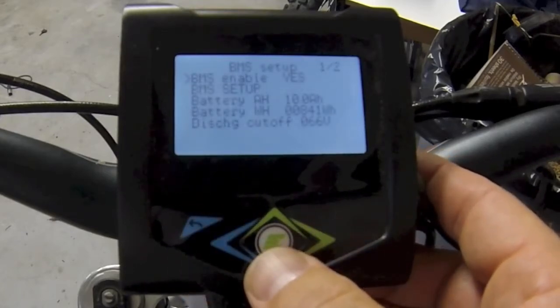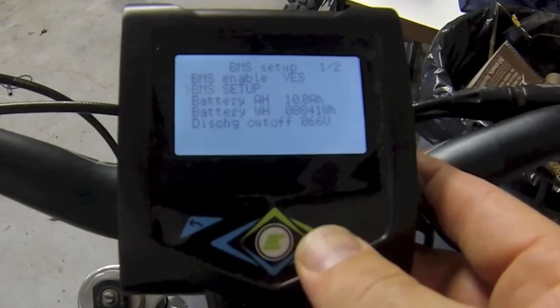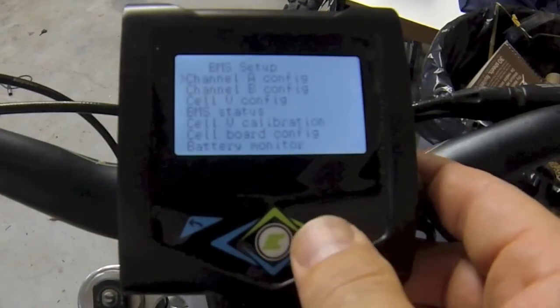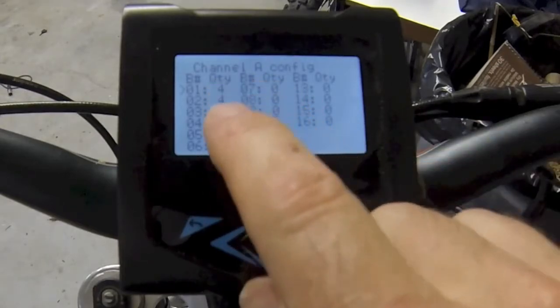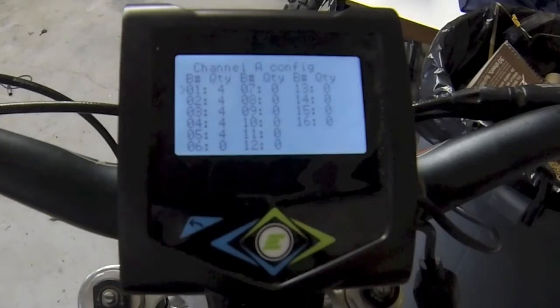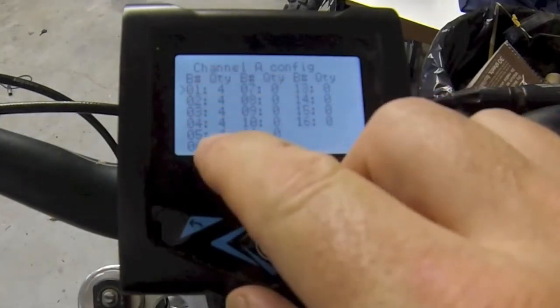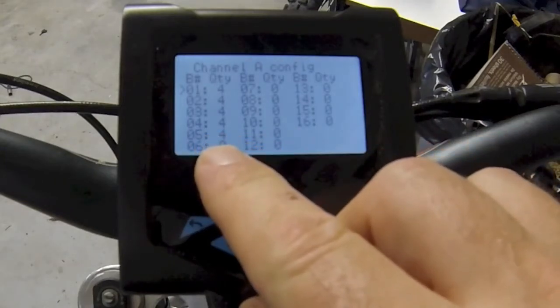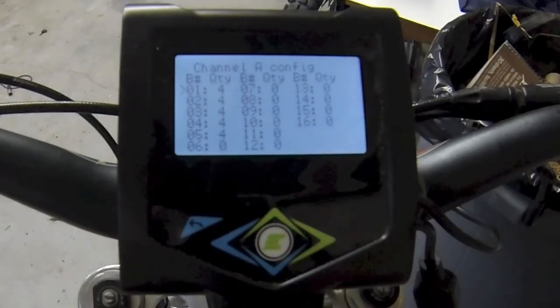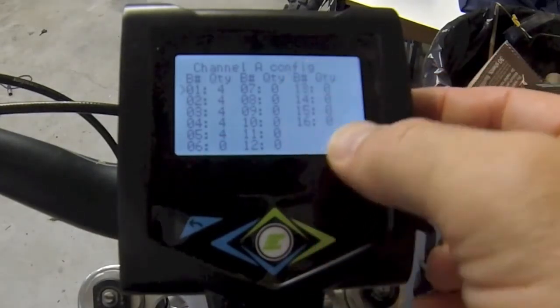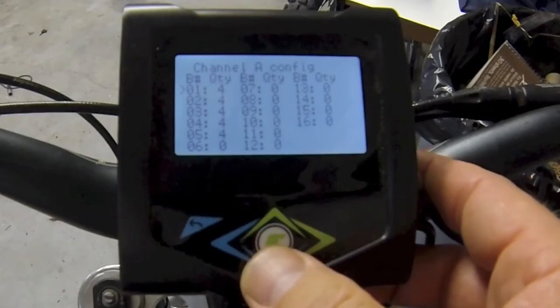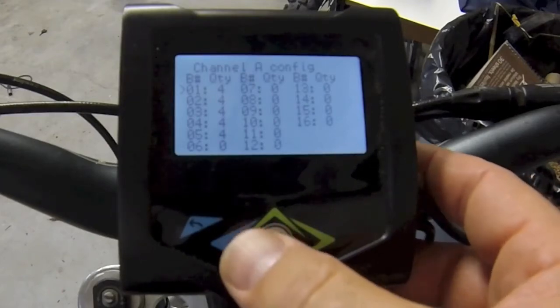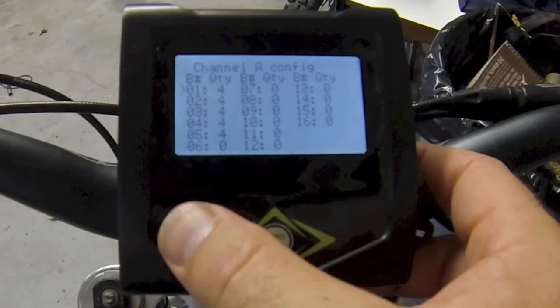Battery setup, okay - BMS enable and BMS setup. So here you go into channel A config. This is where, if you add cells, for each board, each mini board on the BMS, you have to tell it how many cells are on that board. So if you have less than 4 per connector, you need to tell it there. It looks like there's up to 16 boards that can be configured, but we're just using 5 for 20S.